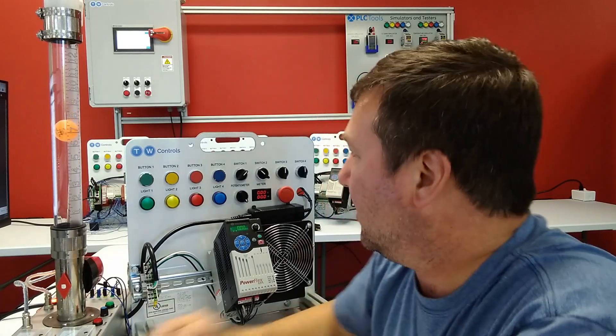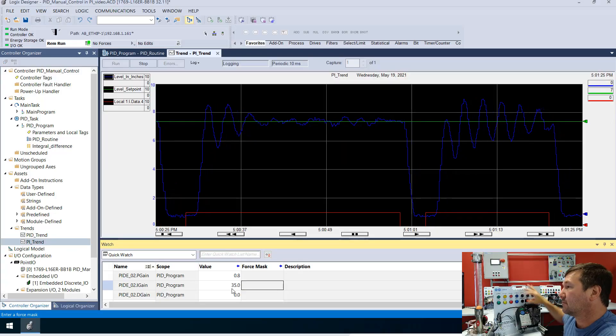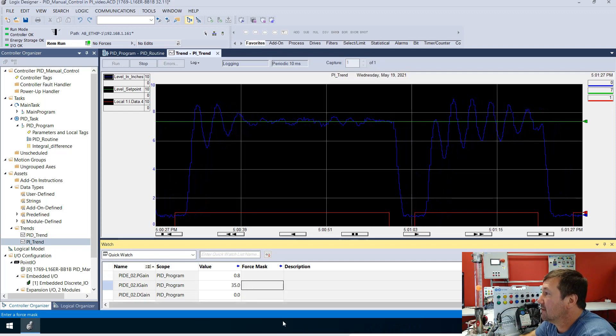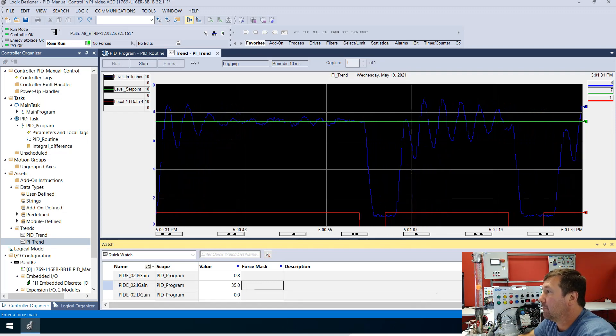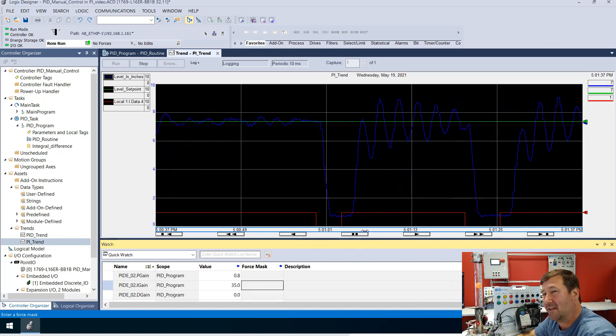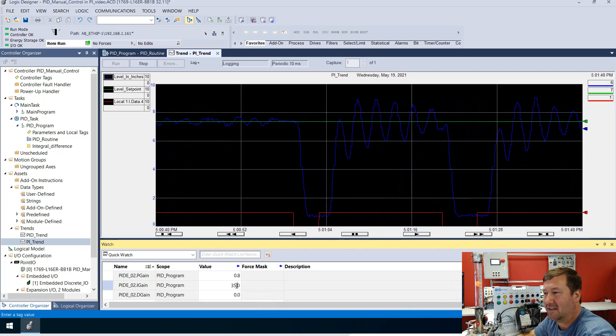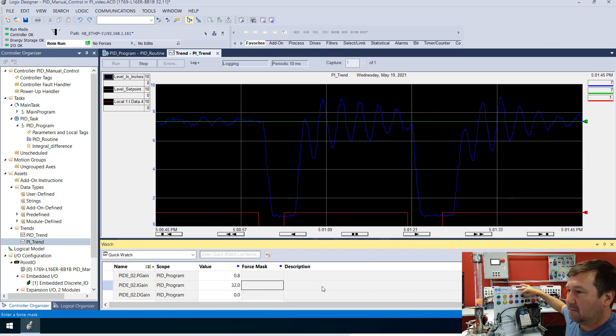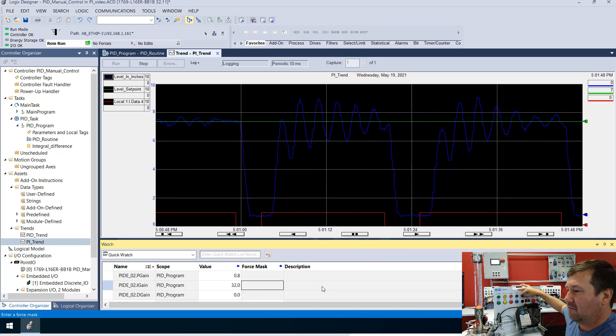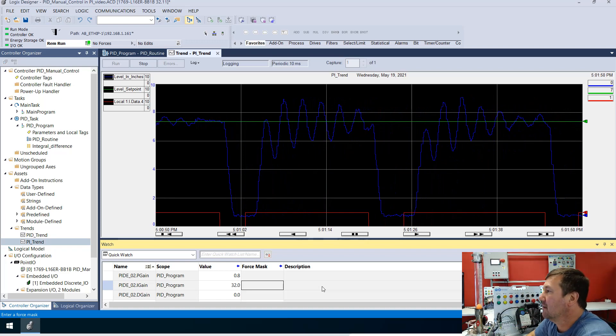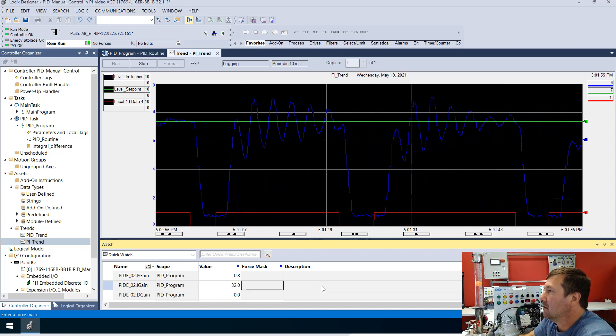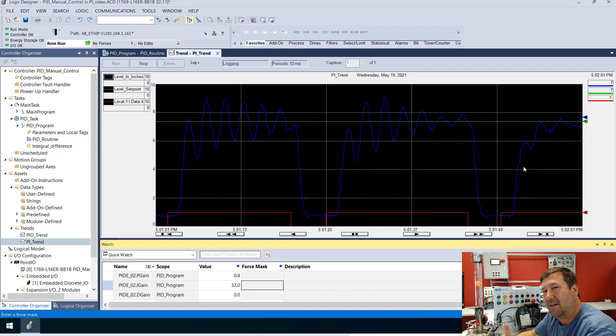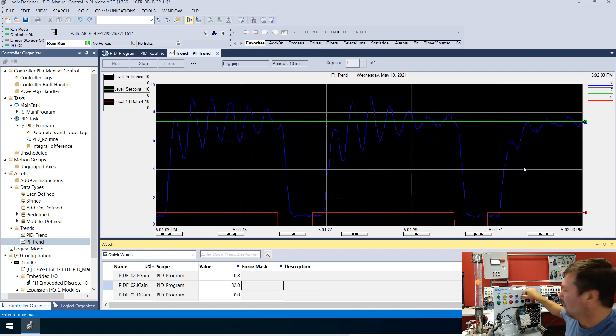All right, you see, we're getting some oscillation here. So I'm going to lower that integral back down. Let's just try 35. Okay, so we're still having a lot of zigzagging. It seems like this 35 is still a little high. I'm going to take it to 32. And let's try it one more time here. Okay, so that came in okay. And we probably could work with it a little more and get it better.